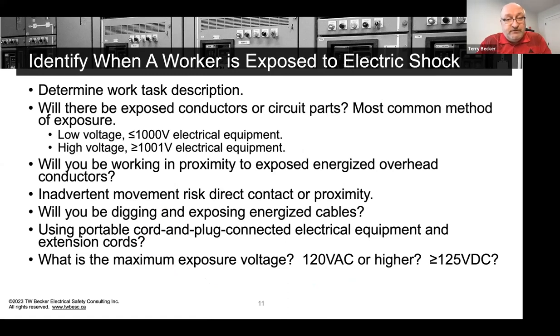So identify specifically when a worker is exposed to electric shock. It starts with the work task again, and will there be exposed conductors and circuit parts with voltage present? And again, the most common method of exposure is that there are exposed conductors and the worker's going in with their hands. They're going with their hands with a test instrument, right? And we're going to use the definitions of low voltage from the National Electrical Code or the Canadian Electrical Code. Less than or equal to 1,000 volts is low voltage. Greater than or equal to 1,001 volts is high voltage.